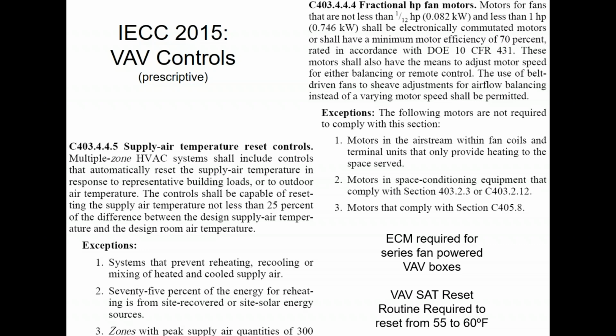If you have VAV controls, you also have to do supply air reset control. So not only are you resetting static pressure for VAV, you also have to reset supply air temperature. Typically, you have to reset this from 55 to 60, right? Because it says 25% of the difference between the design supply air temperature and the room air temperature. And in a 75-degree room with a 55-degree supply air design, that means 5 degrees of reset. So you're resetting from 55 up to 60 degrees.